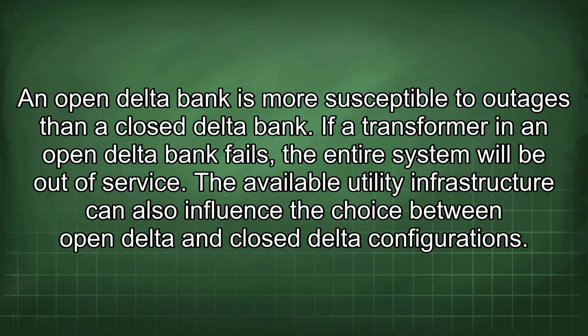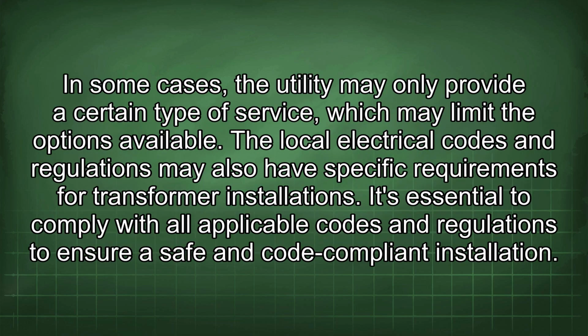The available utility infrastructure can also influence the choice between open delta and closed delta configurations. In some cases, the utility may only provide a certain type of service, which may limit the options available. The local electrical codes and regulations may also have specific requirements for transformer installations. It's essential to comply with all applicable codes and regulations to ensure a safe and code-compliant installation.